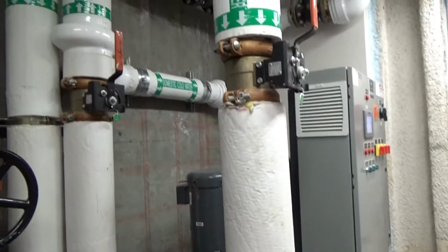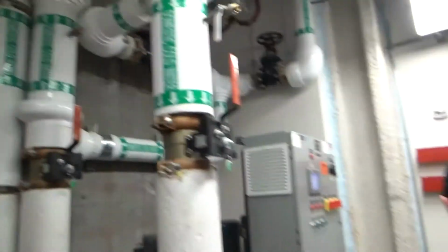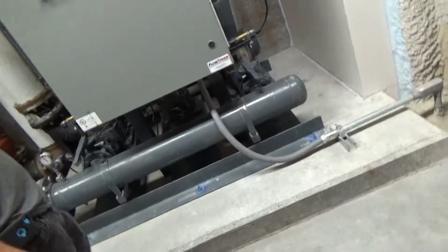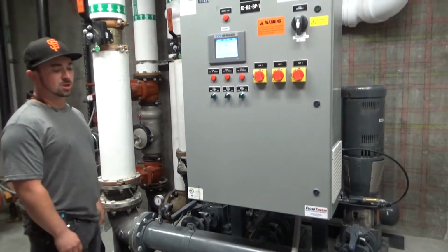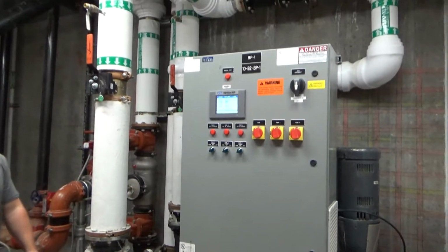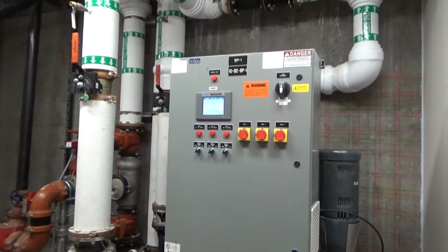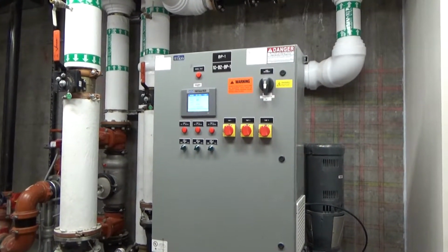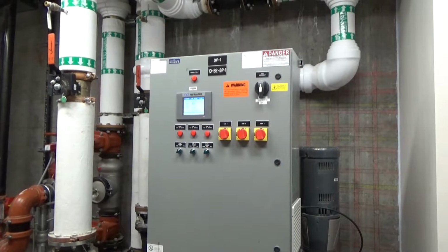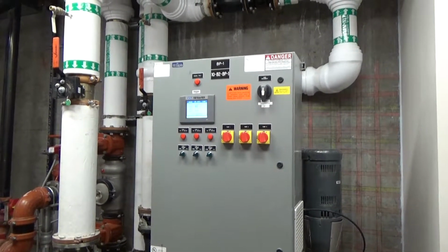So this is considered a triplex system, which means there's 3 different pumps on here. Most of the time the way they size these is they'll do one pump that can handle the whole load and the other 2 are pretty much backups. Most people get duplexes, but if you want to be really safe, you get a triplex, which means you have 2 redundant pumps. You have 2 backups at that point.